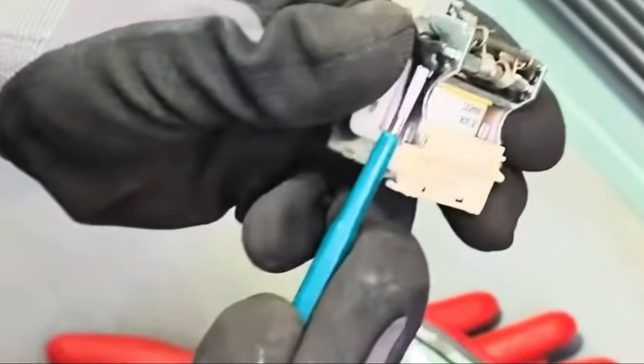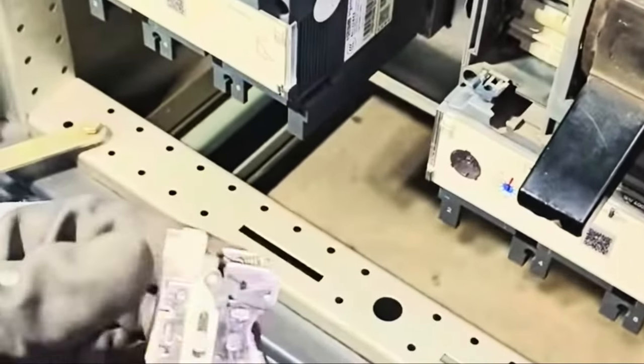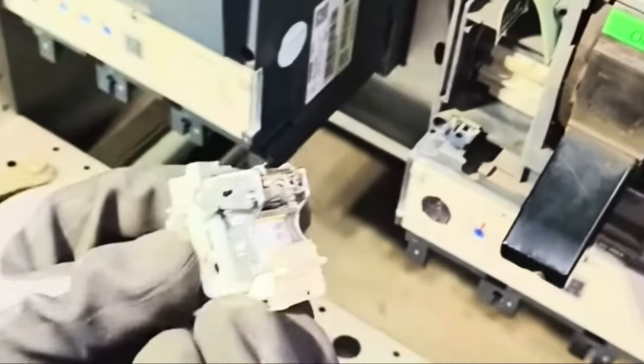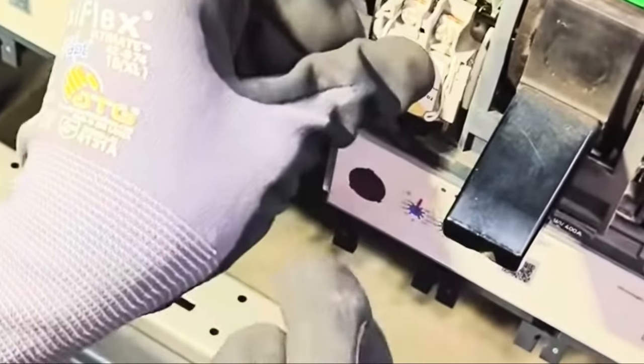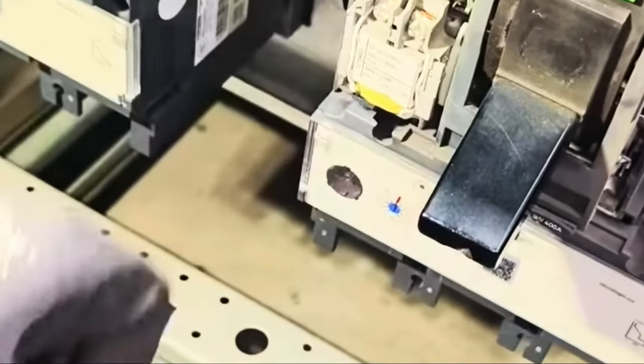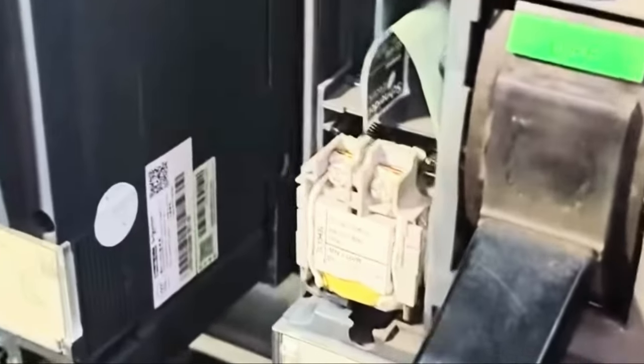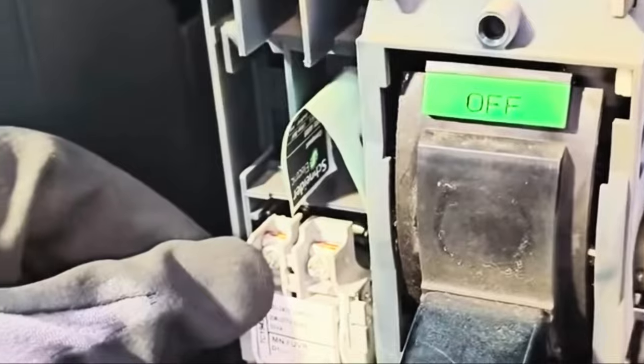Now removing the UVR relay, we found that the closing mechanism of the under voltage relay, which does not allow the breaker to close, is stuck inside. It is only a minor problem inside. The UVR lever is stuck inside. We simply remove the under voltage relay from the MCCB and release that mechanism. Now reset again. It does not have much of a problem.